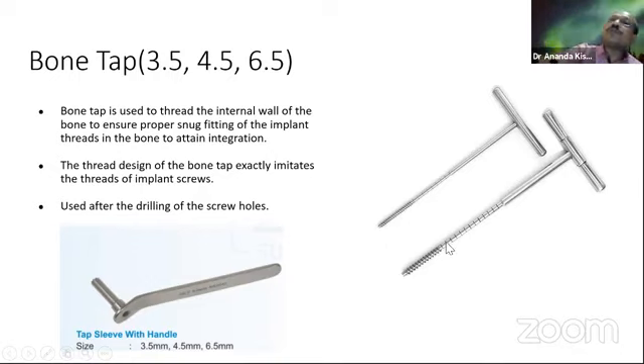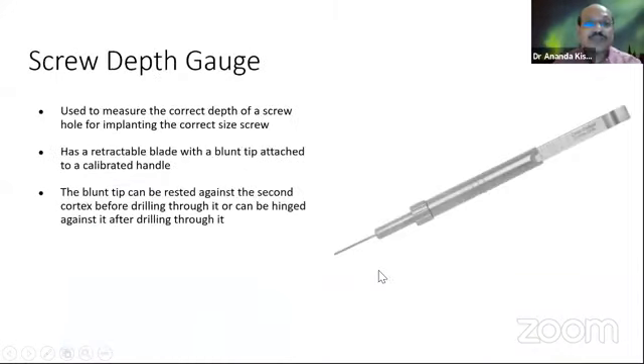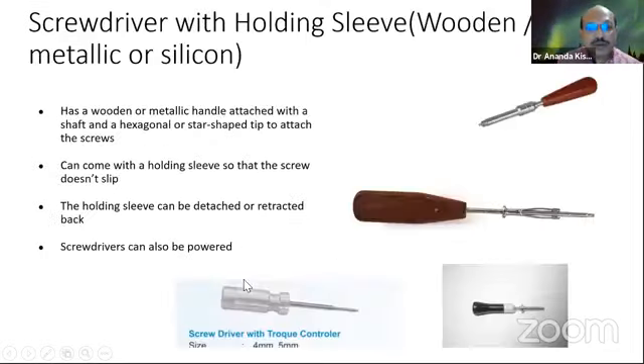If we remove the tap, we just have to reverse the tap. If we reverse the tap, most of the bone debris will accumulate inside these bone channels, and that will come out. So this is the technique that is usually asked. The screw depth gauge is basically used for measuring the exact depth of the screw. I'm not going into detail. There are several types of screwdriver.